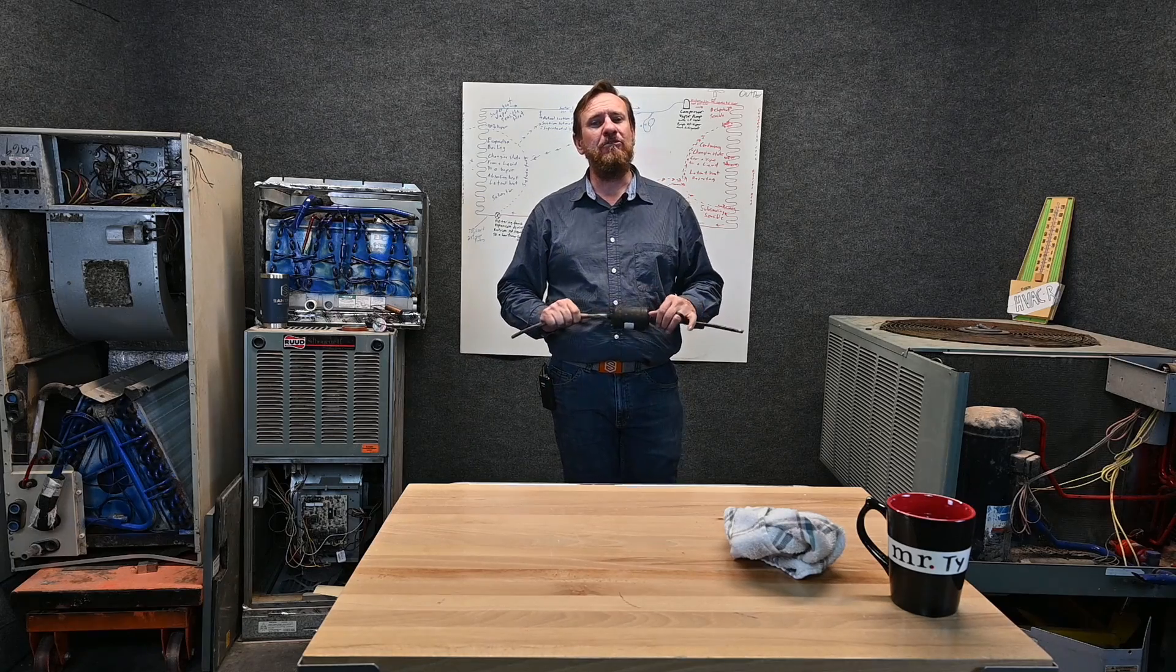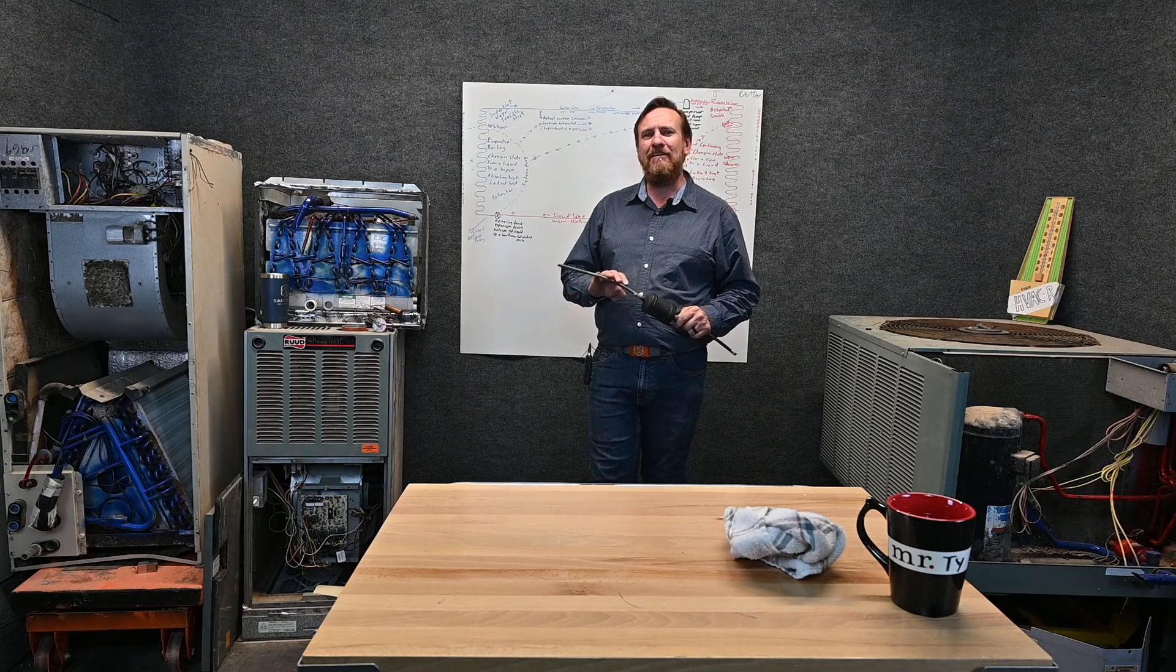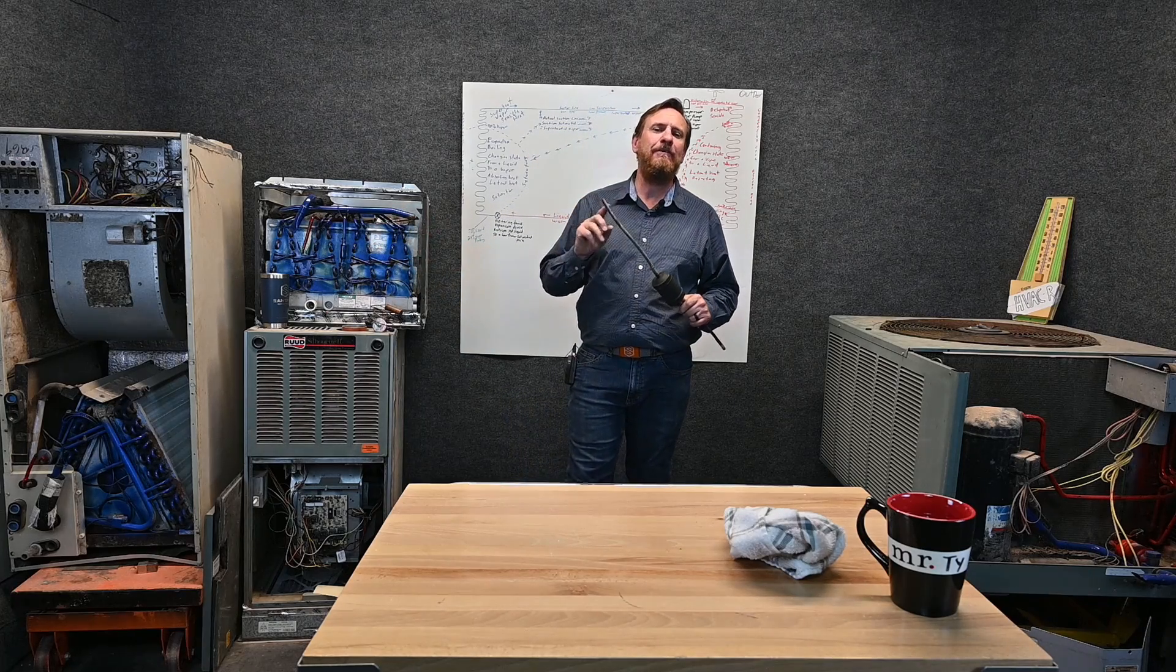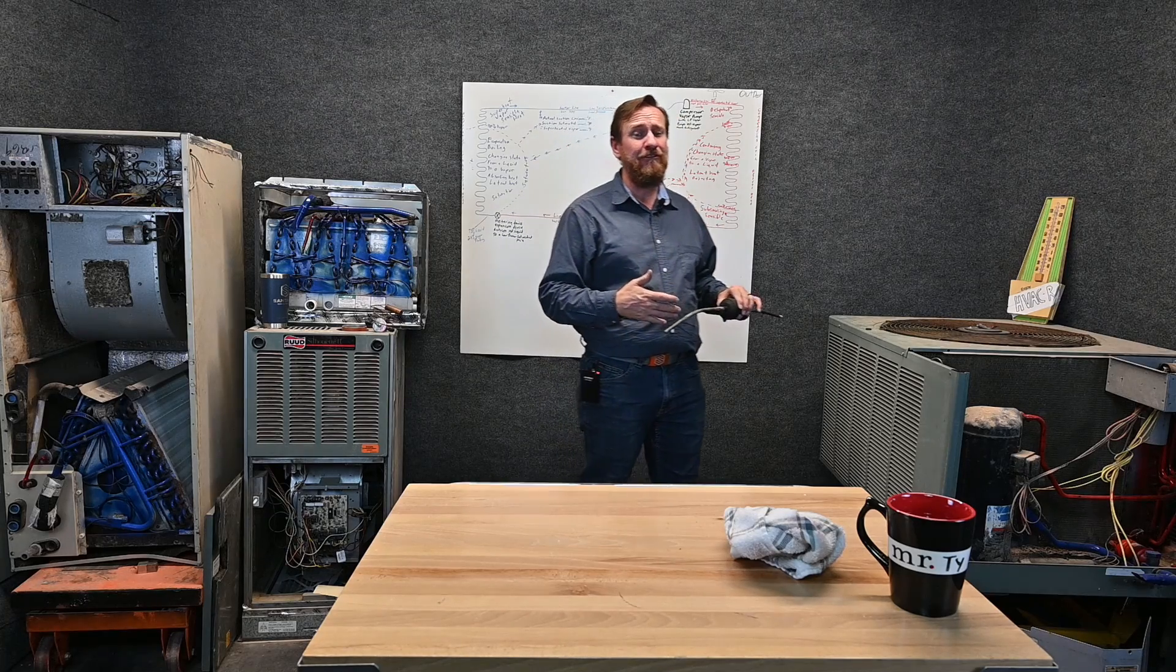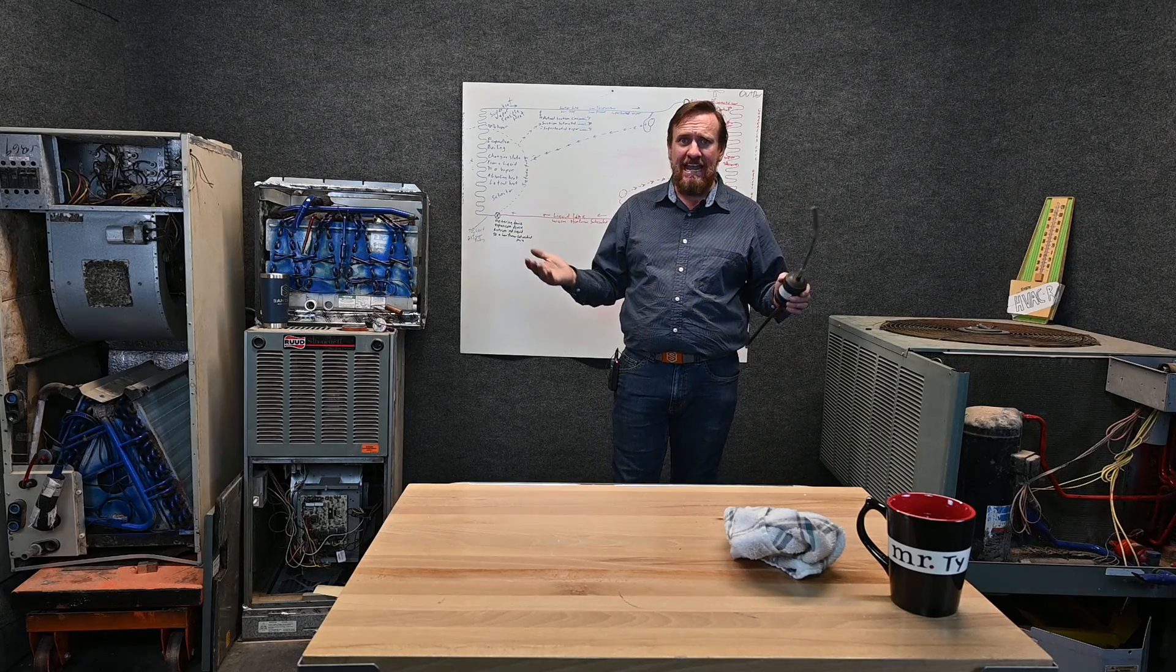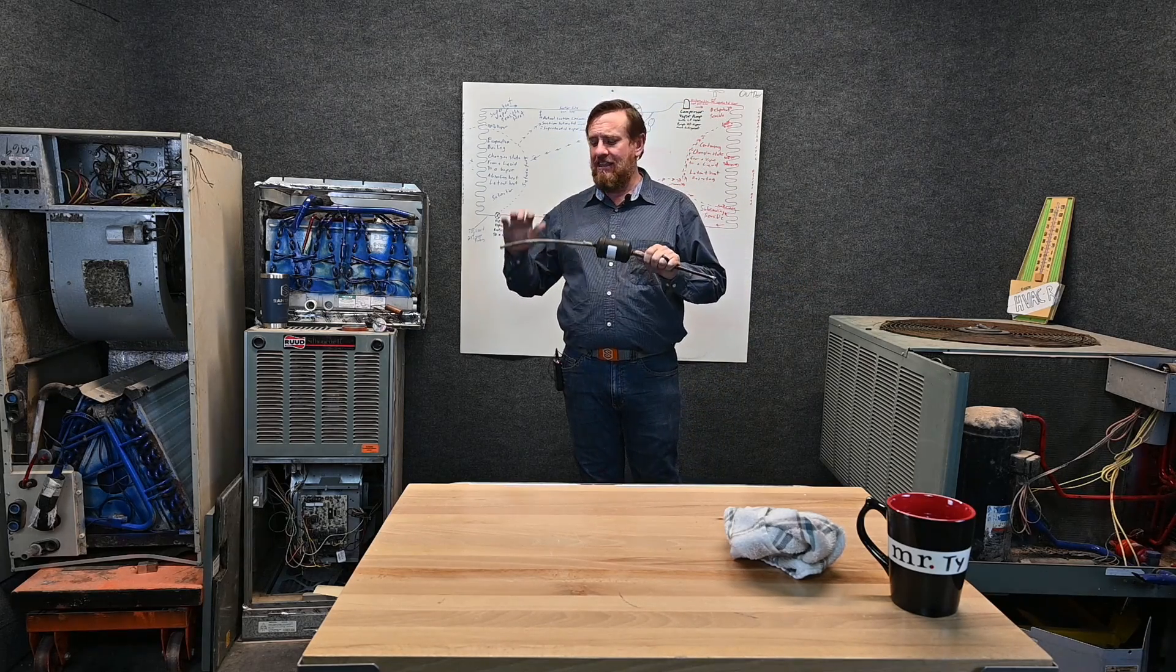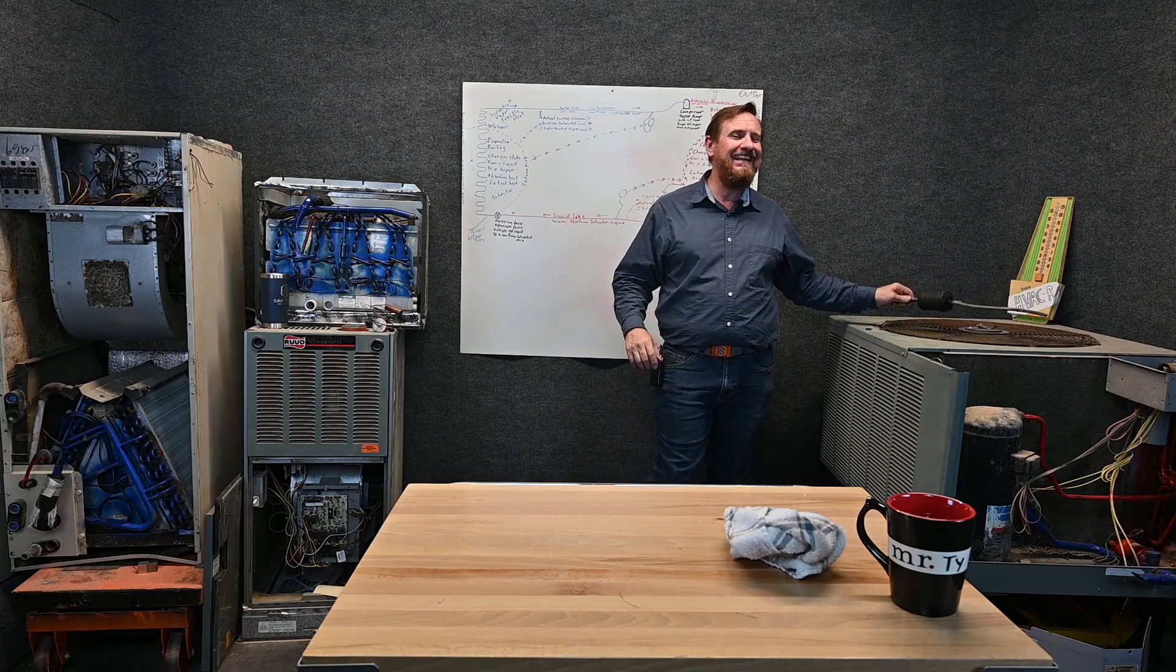On those conditions we want to make sure we insulate this liquid line. Pretty much as a general rule anytime I'm having a liquid line run in the attic I want to make sure it's insulated because I do have the possibility of it losing some of that subcooling. In other words adding sensible heat back to the refrigerant. Subcooling we want to remove sensible heat below saturation. If I put sensible heat back into it such as an attic or some commercial and industrial application we have a lot of heat then you could definitely lose your subcooling.